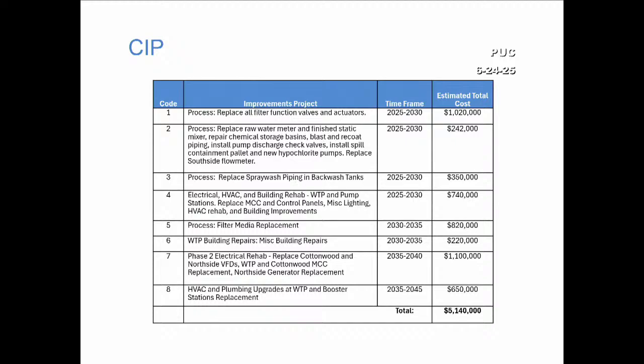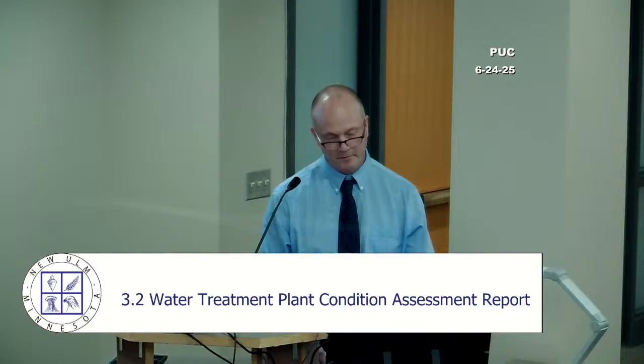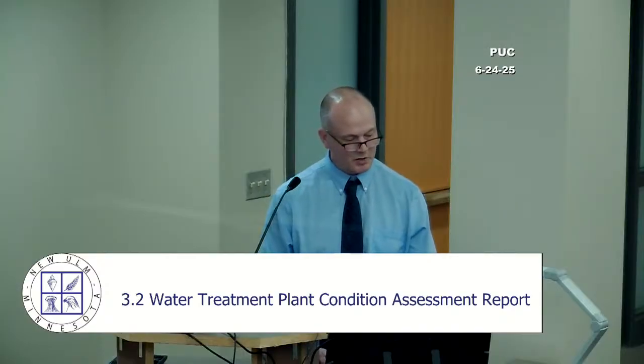So finally, the purpose of this report was to prepare a capital improvements plan. There's a table in the executive summary that goes through and talks about projects that should be done, with an approximate time frame and cost. We have them numbered more by class of projects and time frames, but I mentioned the filter function valves and actuators. That's one that's fairly pressing—if a filter function valve fails, at a minimum you'd have to isolate that filter and shut it down. If it failed, it would likely be fixed under some sort of emergency repair, which is more expensive. There's also an assortment of other process projects.